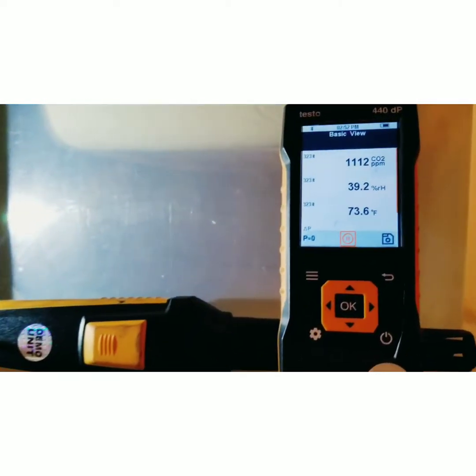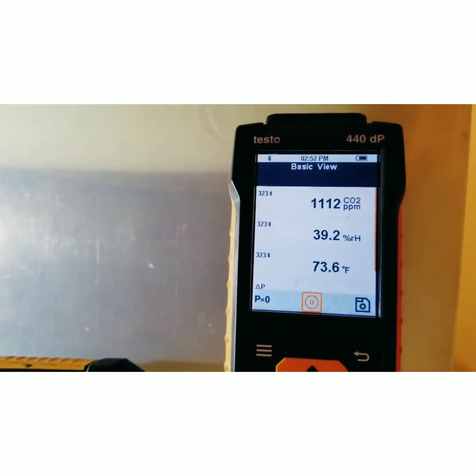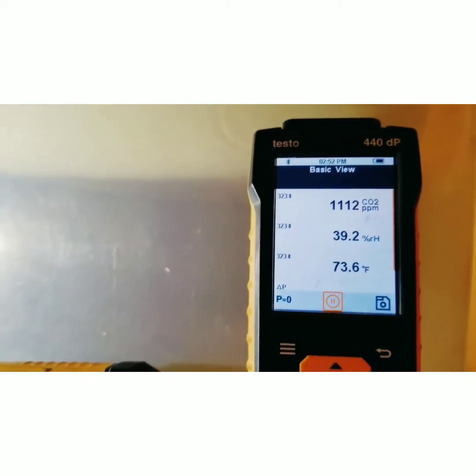The room I'm standing in right now has an air handler. Basically this whole room brings back the return air from the office space. We have a return air boot there that comes in from the office and you can feel some nice airflow there. So in this room, with the return air from the office, we are reading over 1,100 parts per million CO2. Now that is high.